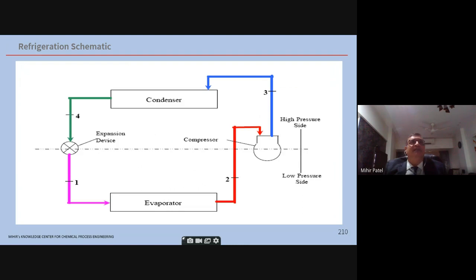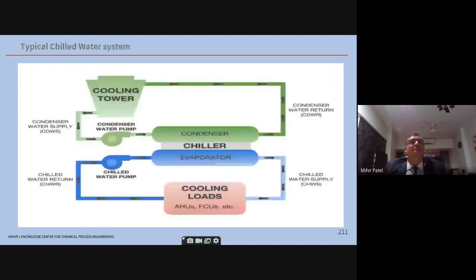Expansion device is there where you are throttling it. The JT effect occurs, the Joule-Thomson effect. Because of the JT effect, you are dropping in temperature, and it goes to the evaporator. In the evaporator, you have the process fluid which is being refrigerated, and then our refrigerant gas evaporates and goes back to the compressors. This is the refrigerant circuit basically. This is again a package item from the vendor.